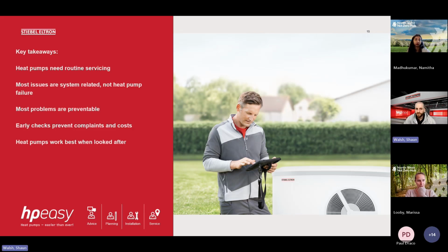Most issues are system related and not actually the heat pump itself. Quite often you'll get, my heat pump's not working. The heat pump relies on all those other system components to make it work, and if they fail, then the heat pump can't run. Okay. Most of the problems are preventable. So most problems with heat pumps are preventable by making sure we clean our filters, there's no air in the system, our diverter valves are working correctly, we've got system pressure, and expansion vessels are charged correctly.